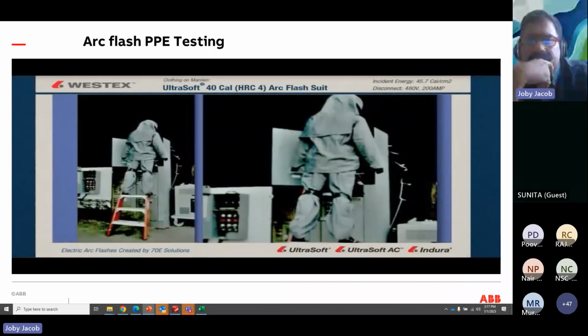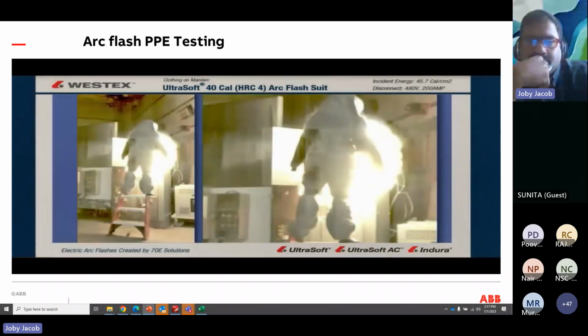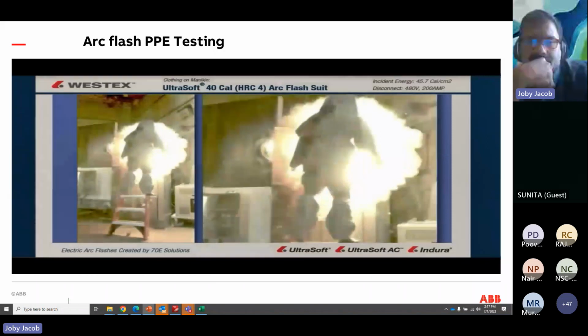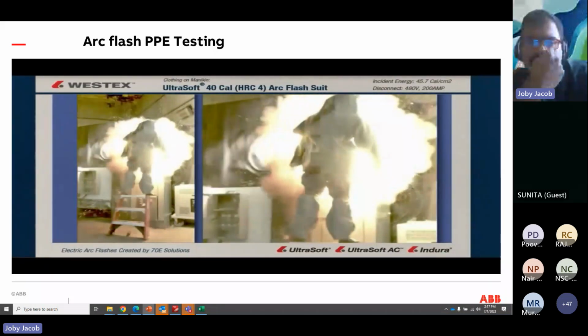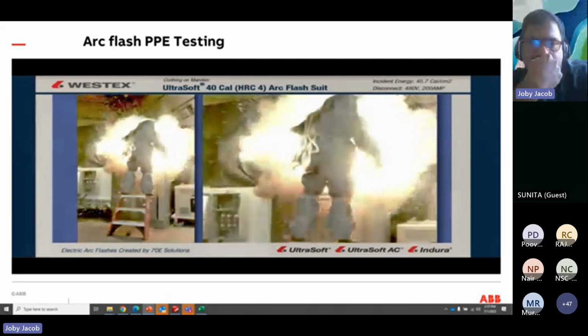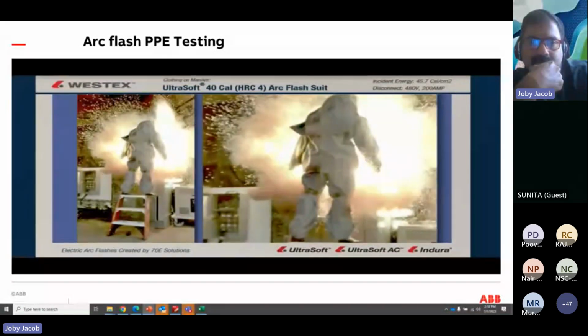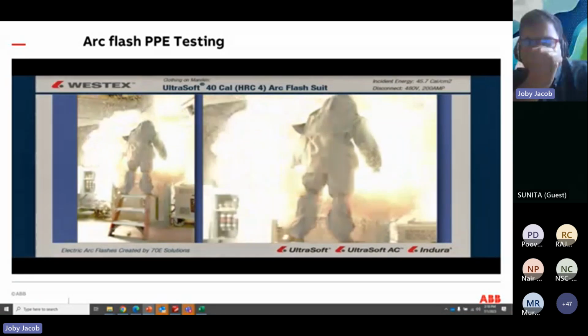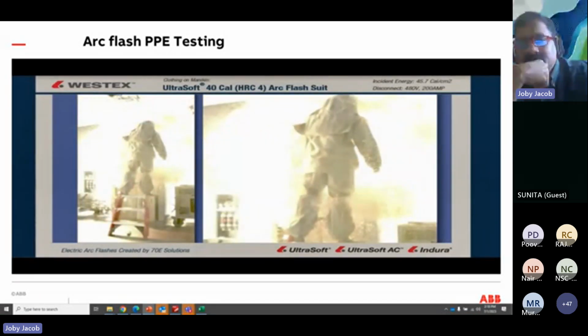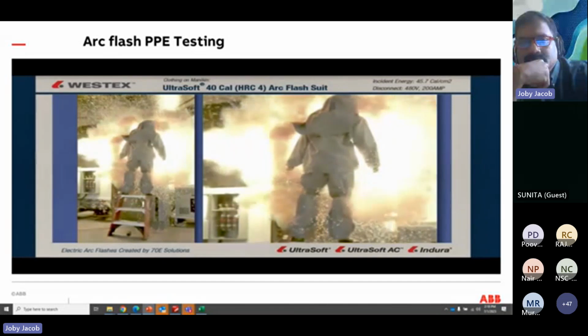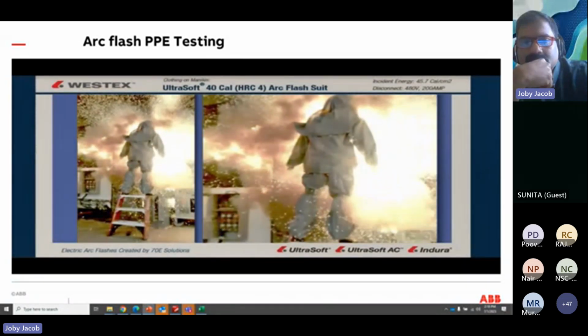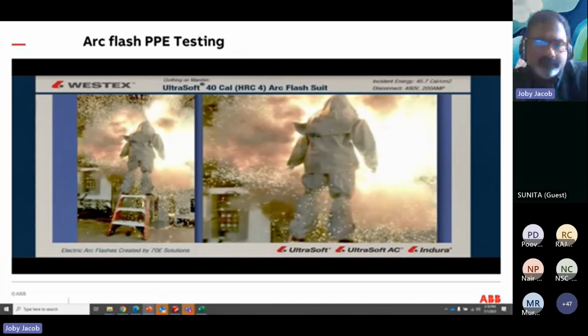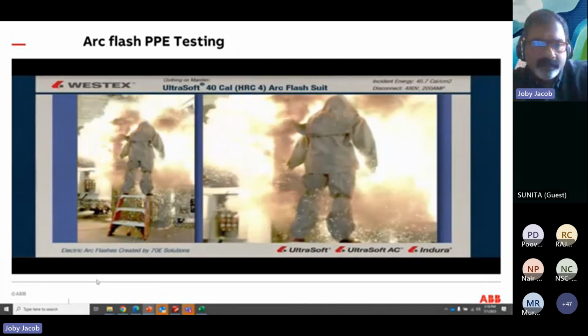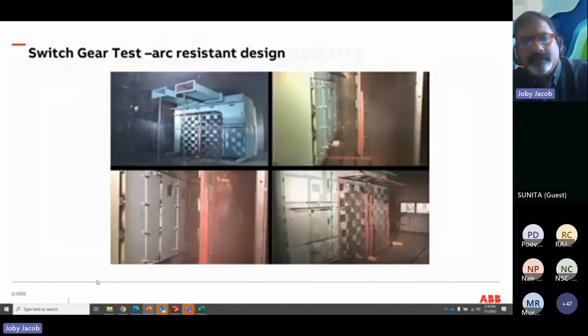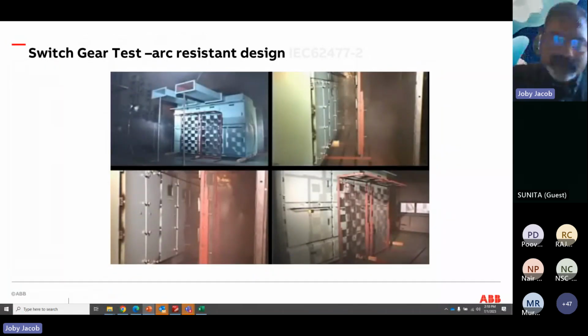We get a look at our split screen slow motion, and at 3,000 frames a second, this is a 14 cycle arc. You get a great look at the pulsing of these cycles, and you see that the molten metal comes out as a wall. There's a wall of molten metal going in all directions, and the arc eventually defeats the sides of the MCC as well, and we get the arc plasma out to the right and left of the mannequin. This is related to the PPE part.